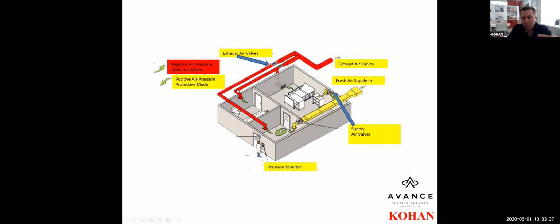the ducts can get mixed up, if you will. So from each room that you require negative pressure, they can go out and get into one ductwork and out. You cannot mix this exhaust with any other exhaust. And where it goes out is very important too. You can't really dump it on the sidewalk or something that's adjacent to other people. It has to be filtered and go out. Even if it's filtered and goes out, it cannot be, let's say, on the side of the street.